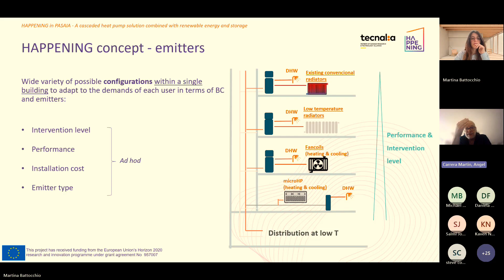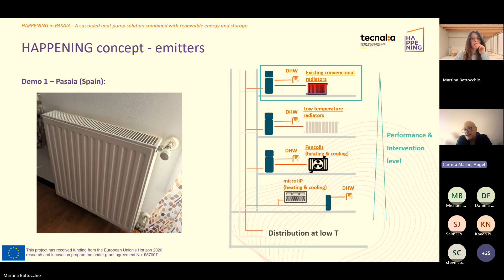The system I'll explain is the Pasaia system, where the main focus was to maintain the existing space heating emitters, conventional radiators as shown in the figure on the left, often operated here in Spain at around 75 degrees. We wanted to keep the existing space heating emitters to minimize disturbance to residents and minimize the cost of the intervention.